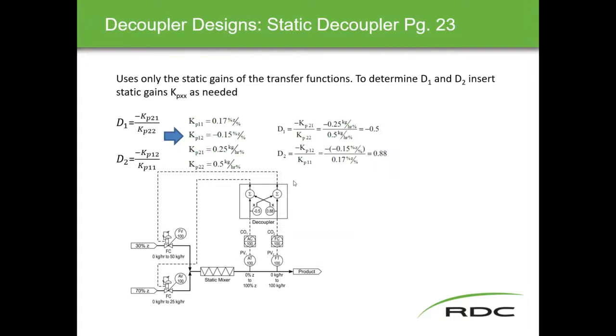With our values from the relative gain matrix and open loop matrix, all we're doing is substituting them into the formula for the decouplers. The decoupler formula: D1 uses PV2 with controller one and controller two, and D2 uses PV1 with controller two and controller one. So KP21 over KP22 — 0.25 over 0.5 for D1, and KP12 over KP11 — 15 over 17 for D2. Simple math gives us our decoupler values, transferred in as D2 for controller two and D1 for controller one.